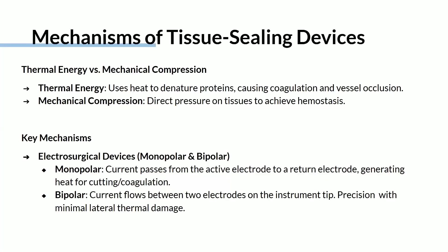When it comes to electrosurgical devices, we have two main types. We have the monopolar and the bipolar devices. The monopolar electrosurgery devices deliver current from an active electrode to a return electrode, or the pad, as we just heard about. They generate heat that we use for cutting and for coagulation. On the other hand, the bipolar devices confine the current between the two electrodes at the instrument tip.